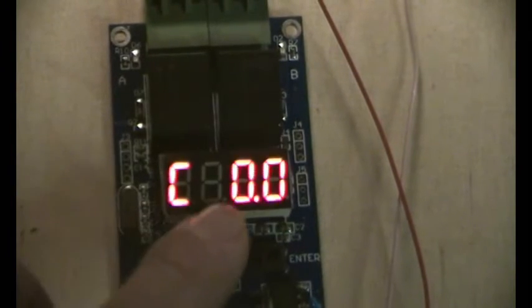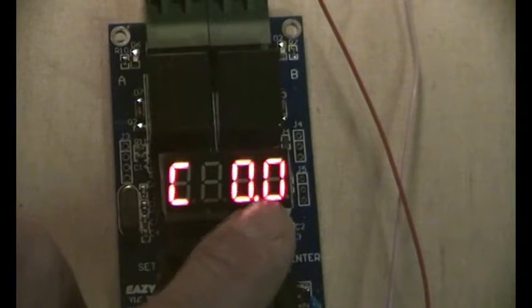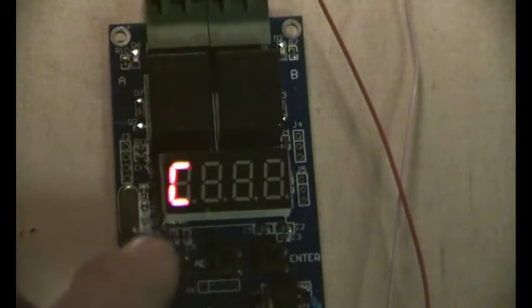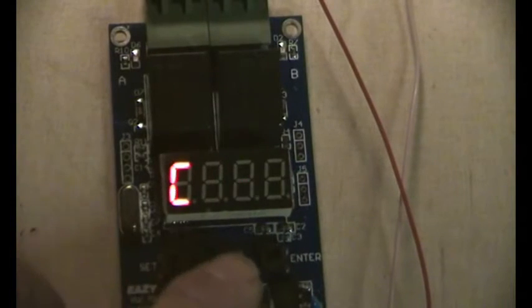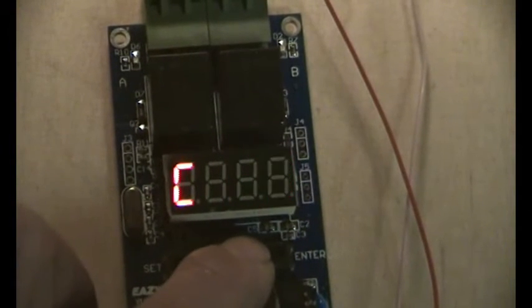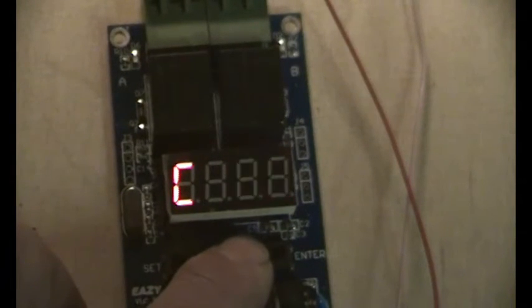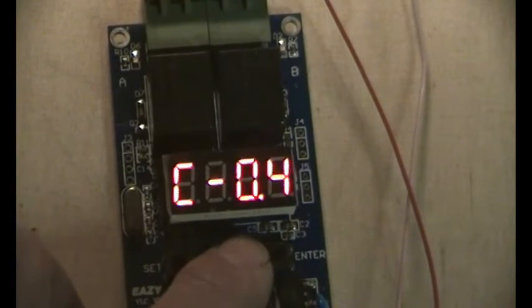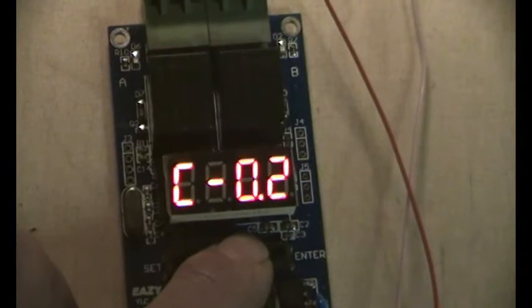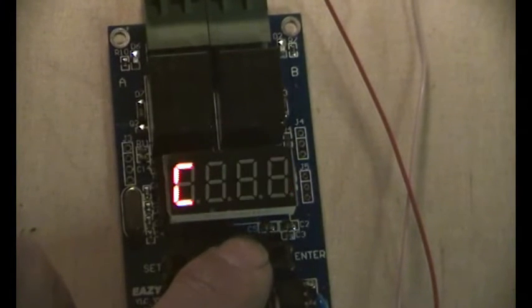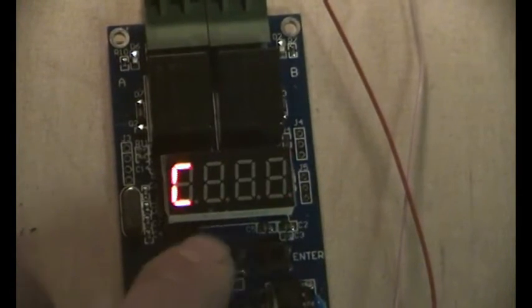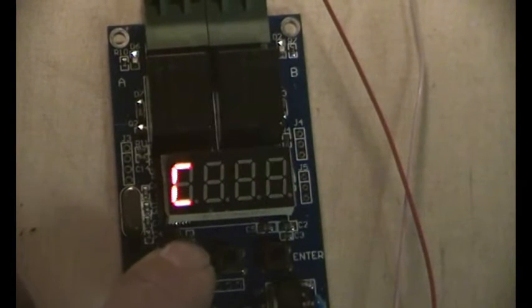That's calibrate, calibrating the switching around the voltage that you've set. So we can just press add, and as you can see, it goes 1, 2, 3, 4, 5, and then it goes into minus. So it's like minus 0.2 of a volt before the figure that you've set for the high. Okay, I'm happy with that.